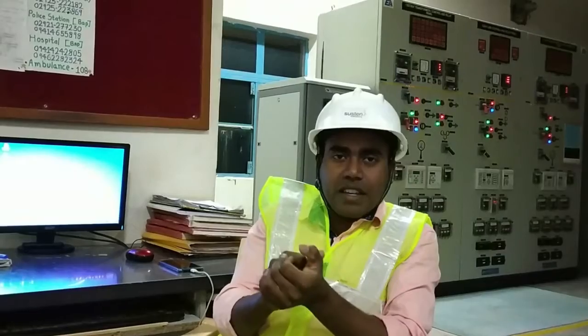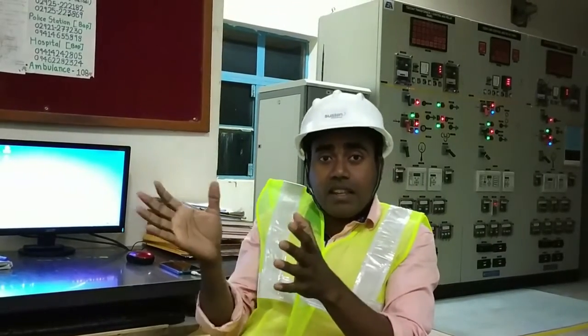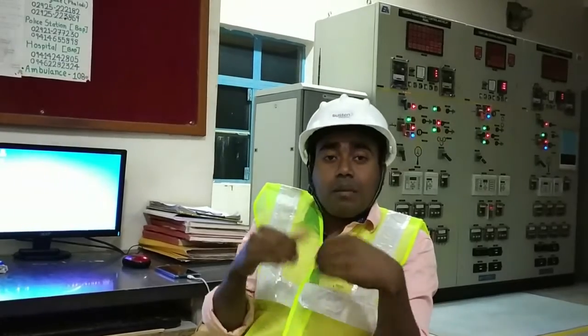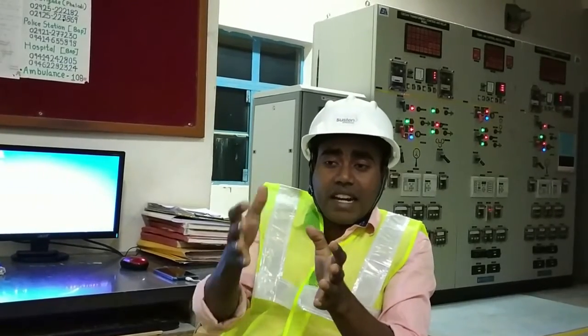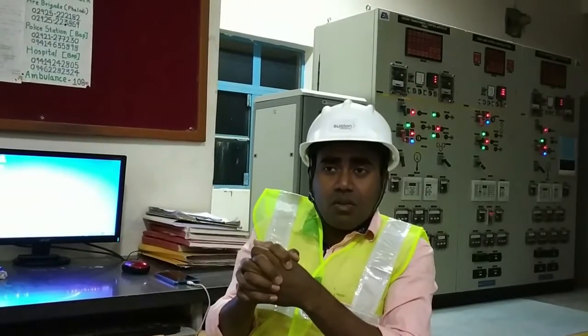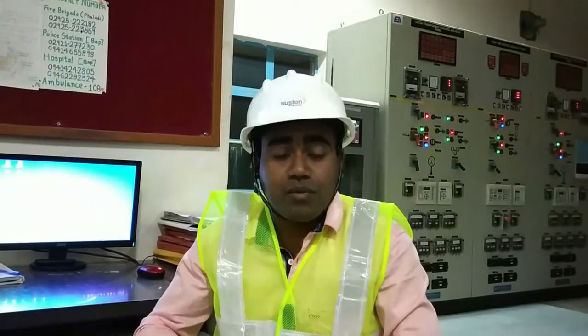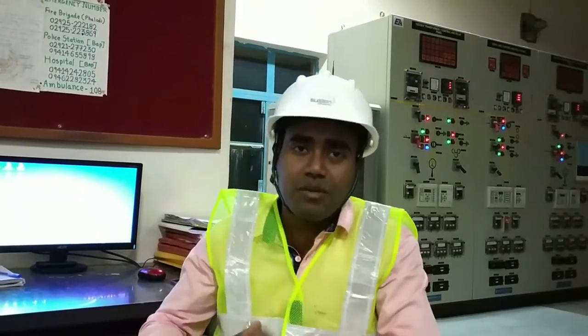My friend is deputed there, and on the day when I went there, this incident happened. One CT, current transformer, blasted, which was installed in the transformer bay in a 400 kV substation. That day we stayed there and we were doing some root cause analysis, trying to find why that current transformer blasted, why it exploded. We found some reasons, and that experience I want to share with you.